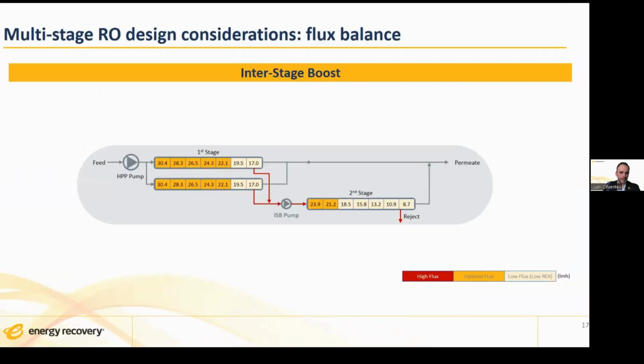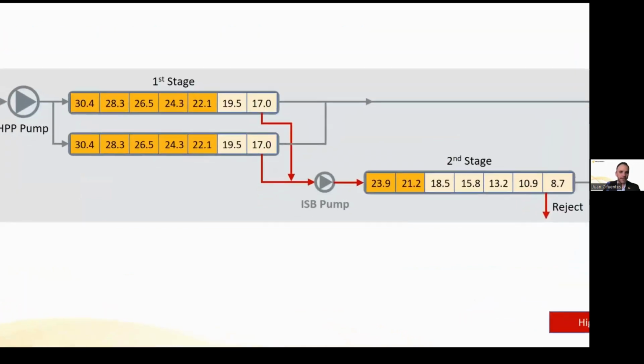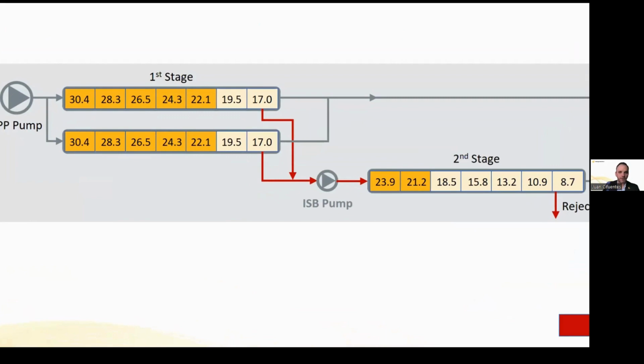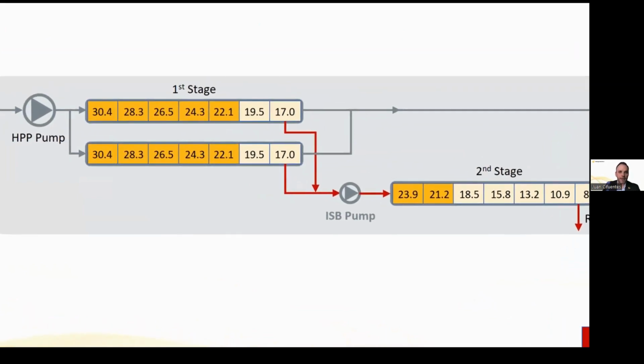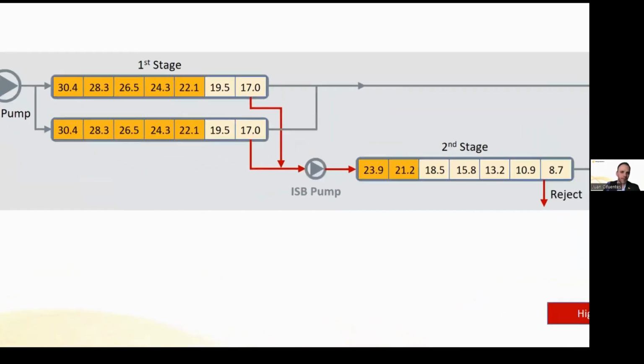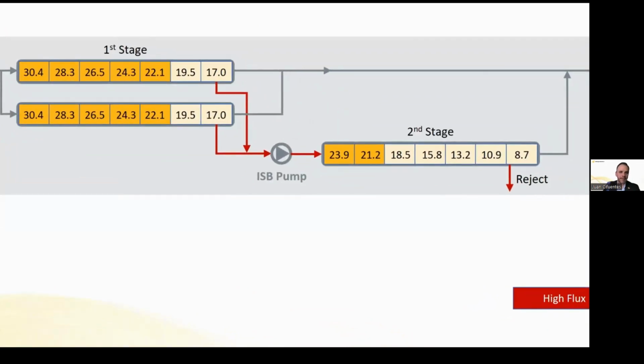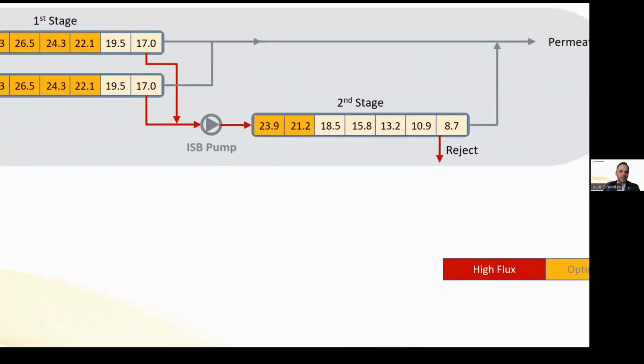And then, if we add an interstage boost, what we can achieve is the same flux distribution, but the high pressure pump has just to provide the pressure required in the first stage, and the interstage boost pump only pressurizes the second stage feed. Therefore, we are further improving the efficiency of the system.